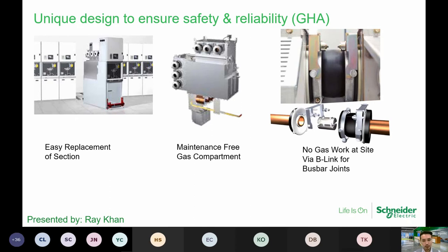So the addition of the adjacent panel has been made easier, especially for extension. All right, so what it does is that we actually have the connection of the bus bar done via this B-link system. The B-link doesn't require any maintenance and it works on the IP65 system.